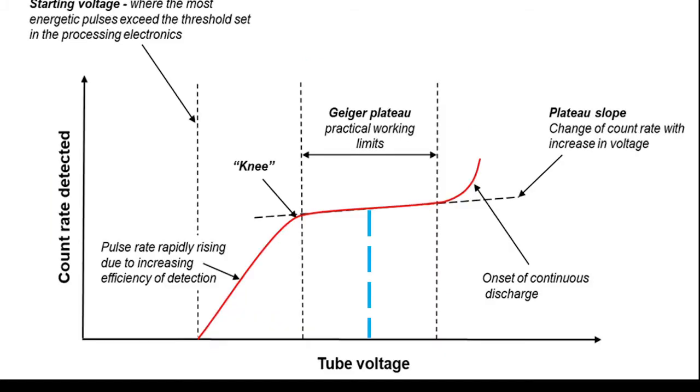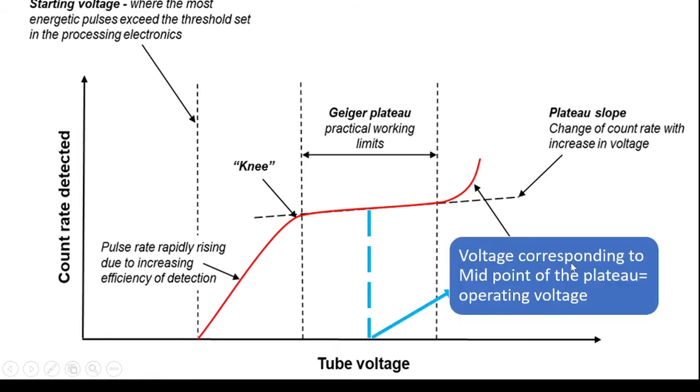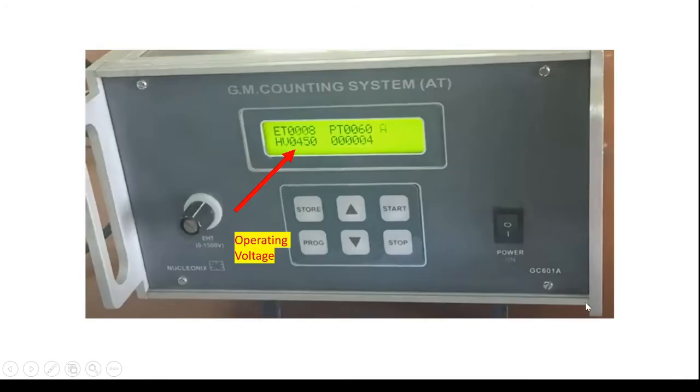Now every GM counter will have a characteristic curve which is represented in this particular diagram. This part which is basically the midway through the plateau length is going to be corresponding to a voltage which is going to be called as the operating voltage. So in the GM counter system which we are using, the operating voltage is set here which you will be able to see as 450 volts.